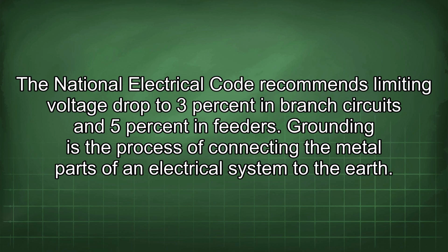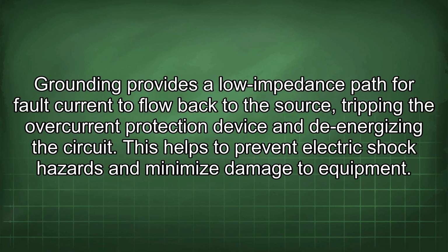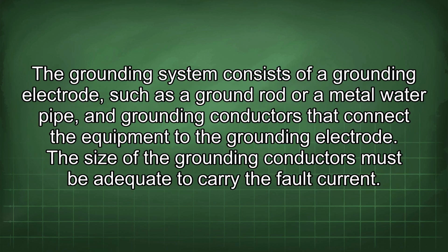Grounding is the process of connecting the metal parts of an electrical system to the earth. Grounding provides a low impedance path for fault current to flow back to the source, tripping the overcurrent protection device and de-energizing the circuit. This helps to prevent electric shock hazards and minimize damage to equipment. The grounding system consists of a grounding electrode, such as a ground rod or a metal water pipe, and grounding conductors that connect the equipment to the grounding electrode. The size of the grounding conductors must be adequate to carry the fault current.